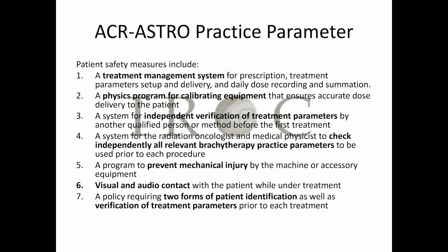You guys have heard us talk about clearance a whole lot, and that is what they're talking about here, preventing a mechanical injury to the patient. And then just common sense, good practice, you would want to both hear and see your patient when you're treating them, because you're not in the room with them. So if you don't have audio and visual contact, you cannot treat, because it's not safe for the patient. If anything happens, you would never know until you open that door again, right?